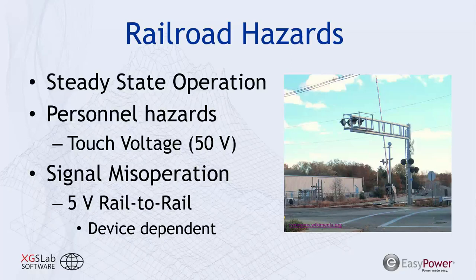It could be as little as 5 volts difference between one rail and another at that 60 hertz that can cause enough voltage imbalance for the signaling to not operate properly. And that could be an issue that allows the arms, such as this grade crossing arm, to come down at times when there is no train, which creates another public safety hazard as people start to drive around those arms as they no longer have confidence in the train signaling and could cause a train and vehicle collision.